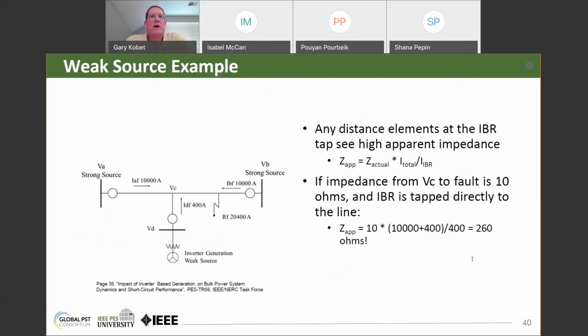Another issue is weak sources. In a case where I have a transmission line between two strong sources, and a tapped connection of an inverter-based resource somewhere along that line, and there's a fault near one of the terminals, let's say the actual impedance from location VC to the fault is only 10 ohms. But the impedance that the relay at location D, where VD is located, measures will be magnified by the infeed from the strong source to the left at VA. That relationship is given there, and the relay at VD will actually measure 260 ohms instead of 10 ohms.